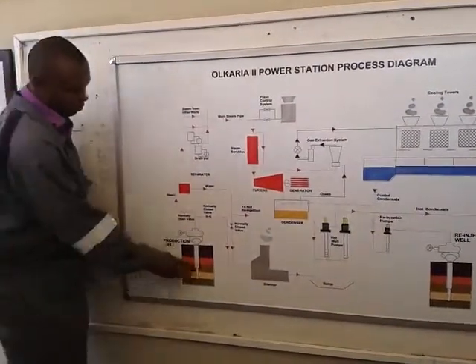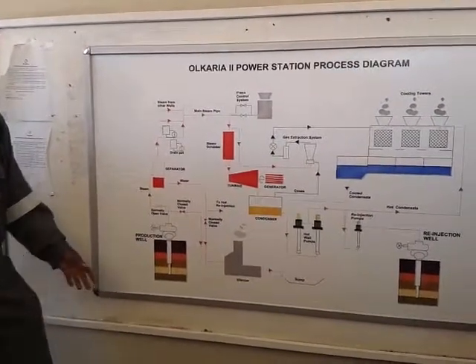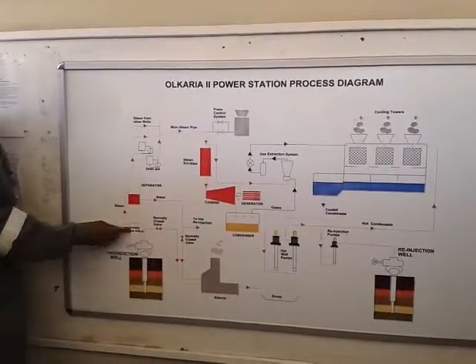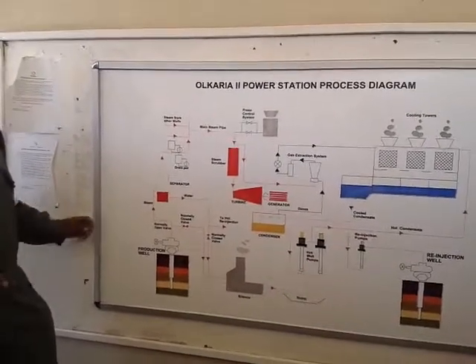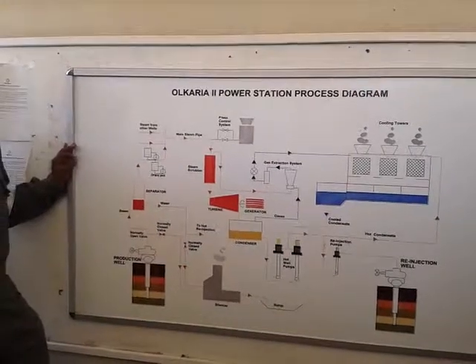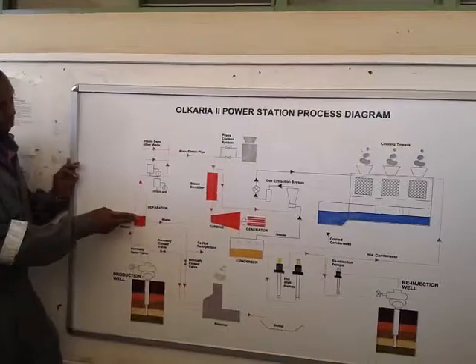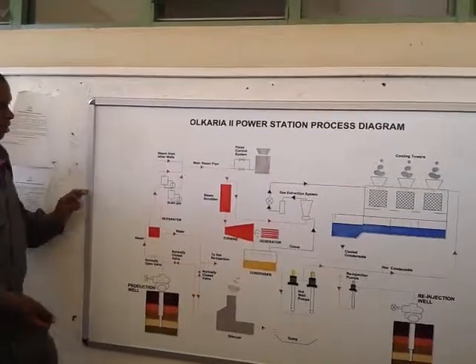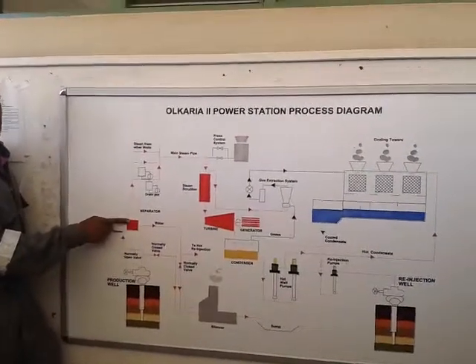Because of pressure, they don't need a pump — a pump that will use energy. It flows on its own. Then it flows to the separator. That mixture of steam, plus water, plus gases — the separator will separate steam from water. It operates on the principle of density. Water is denser than steam, so it remains at the bottom of the separator.